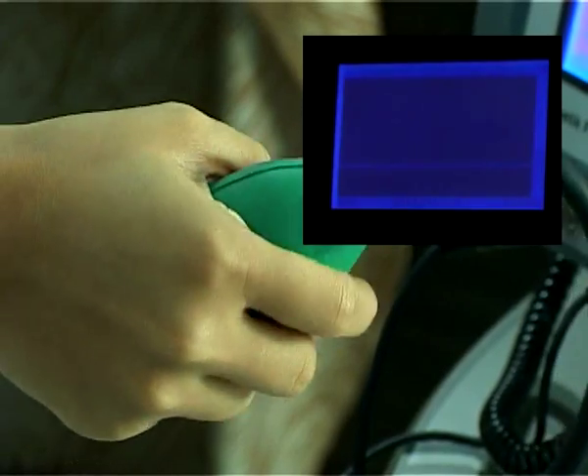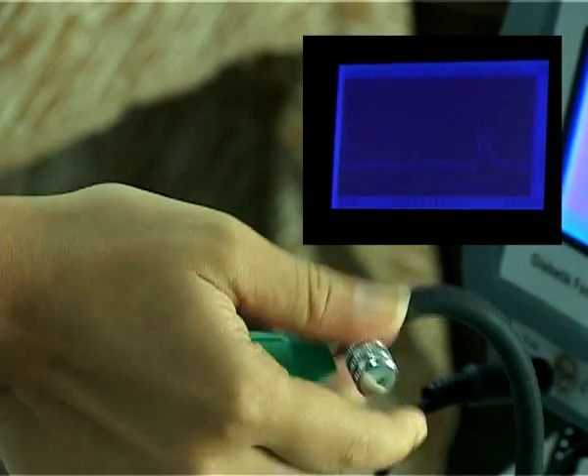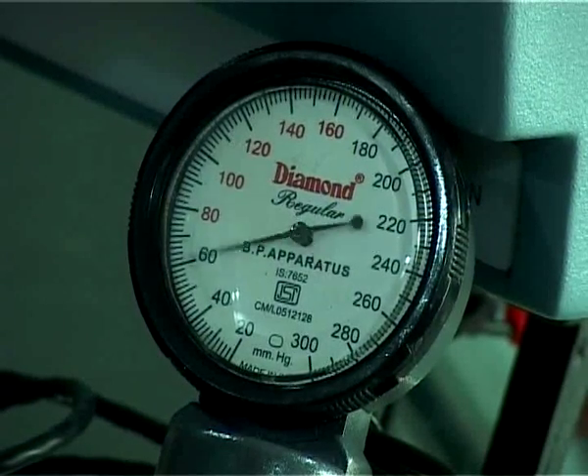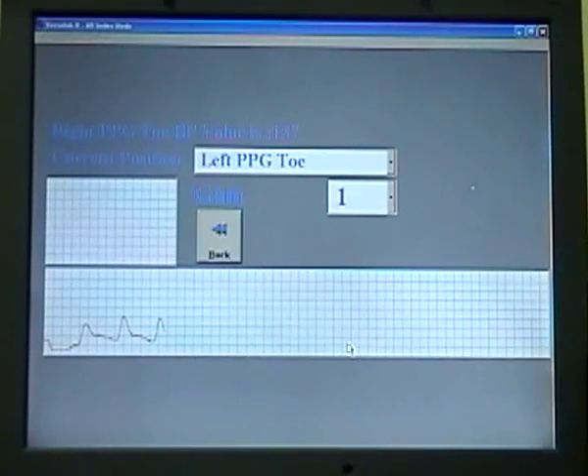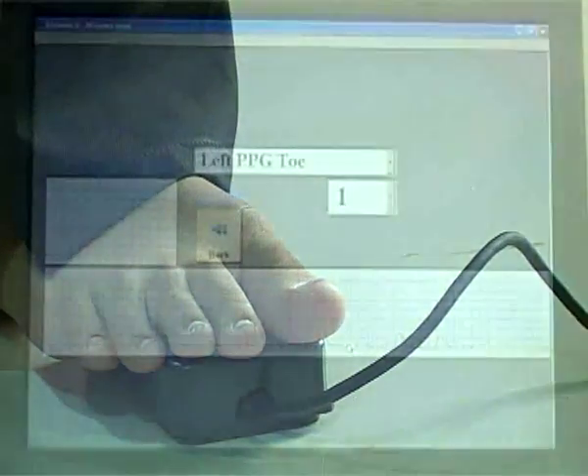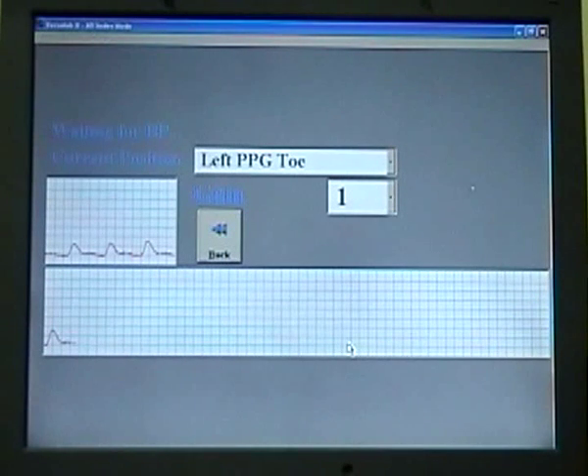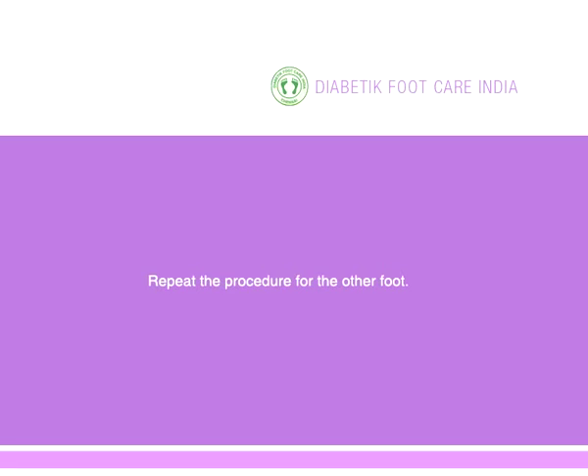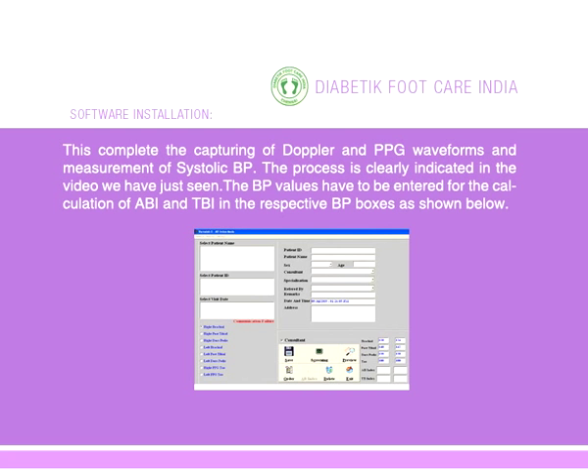Slowly inflate the cuff till the waveform becomes a straight line. Slowly deflate the cuff and note the BP at the first appearance of the waveform. Wait for about 5 seconds and allow the waveform to stabilize. Record the waveform by using hand switch or foot switch. Repeat the procedure for the other foot. This completes the capturing of Doppler and PPG waveforms and the measurement of systolic BP.